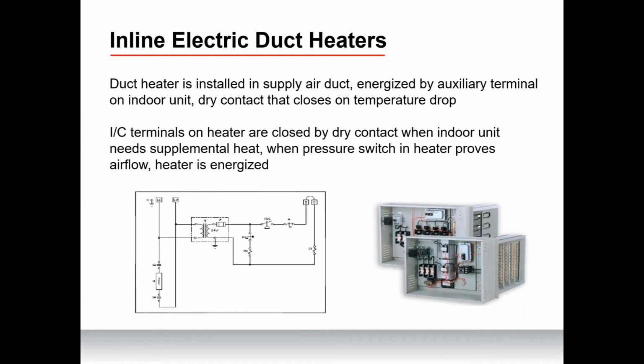We require a small 24-volt relay kit at the heat pump indoor unit and a standard system controller. The system is then wired in as first stage heat pump, second stage electric heat. There are many manufacturers of duct heaters with options of either on-off heaters or ones with modulating capability for increased efficiency. Check with the manufacturer first to ensure compatibility. So if you're dealing with a Mitsubishi system, check with someone from Mitsubishi to ensure compatibility with that inline duct heater. Most of them are going to work. This is a great application if you're utilizing a horizontal ducted system. It's pretty seamless as well. It's not that hard to do. Since it is a third-party product, it doesn't integrate as seamlessly as that electric heat kit. However, it's very, very easy to do just by doing what we said there. It's not that complicated when it comes to that inline electric duct heater. And these can supplement then the BTU loss that you need.